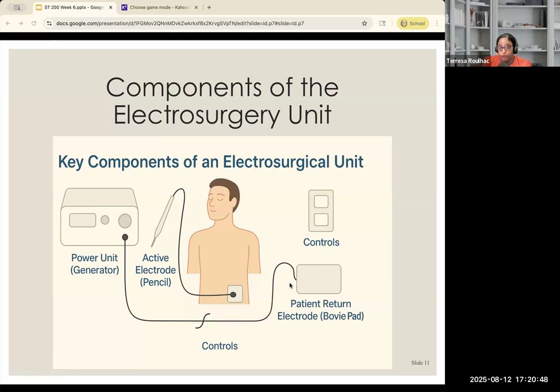Now, there are two types that we use, and the chapter wants you to know, so there's no better way than breaking it down. You have monopolar. Current flows from the active electrode through the patient's body out through that Bovie pad, grounding pad, or the patient return electrode. You may see all three terms or one term, but it's important to know that when you're talking about the patient return electrode, you're talking about the Bovie pad, also called a grounding pad. The three are synonymous. Your Bovie pad, again, is placed on a large muscle area, preferably, to safely return current and prevent burns.